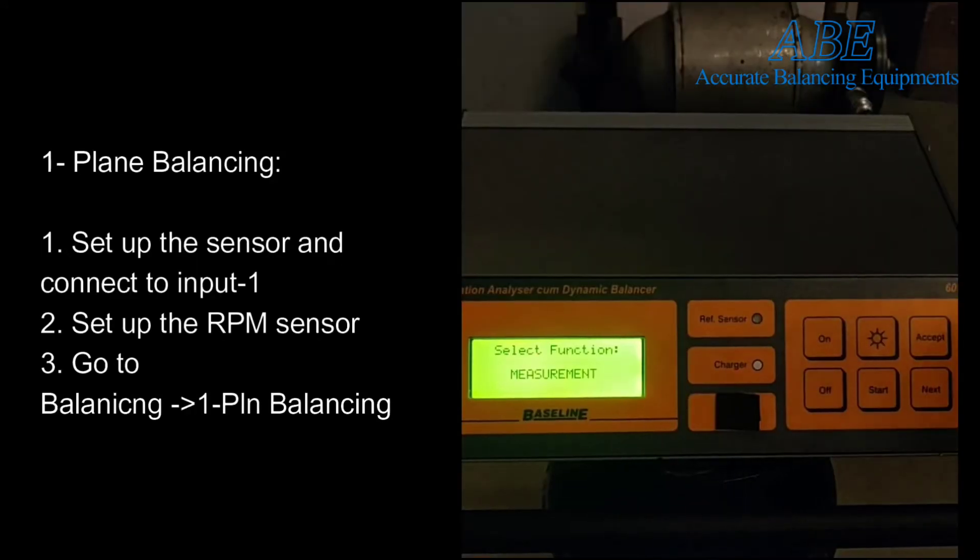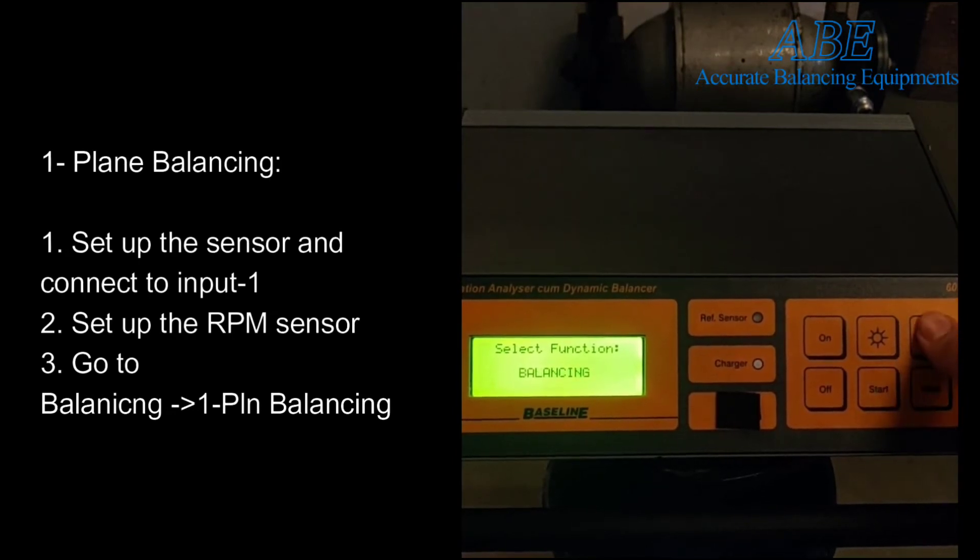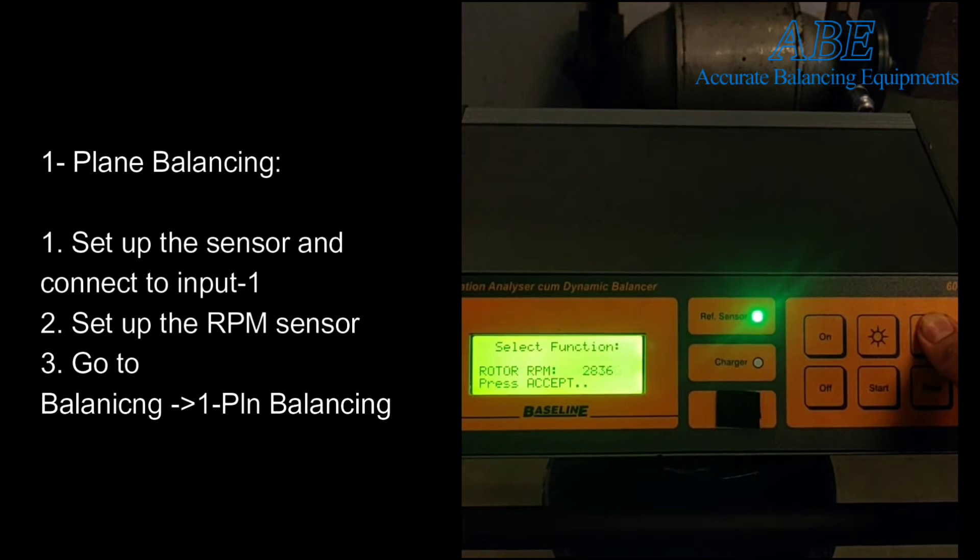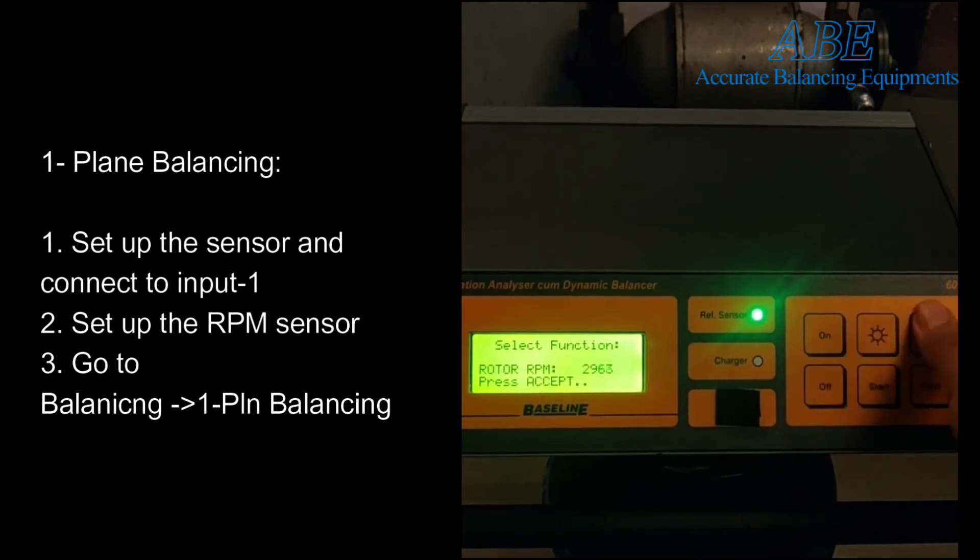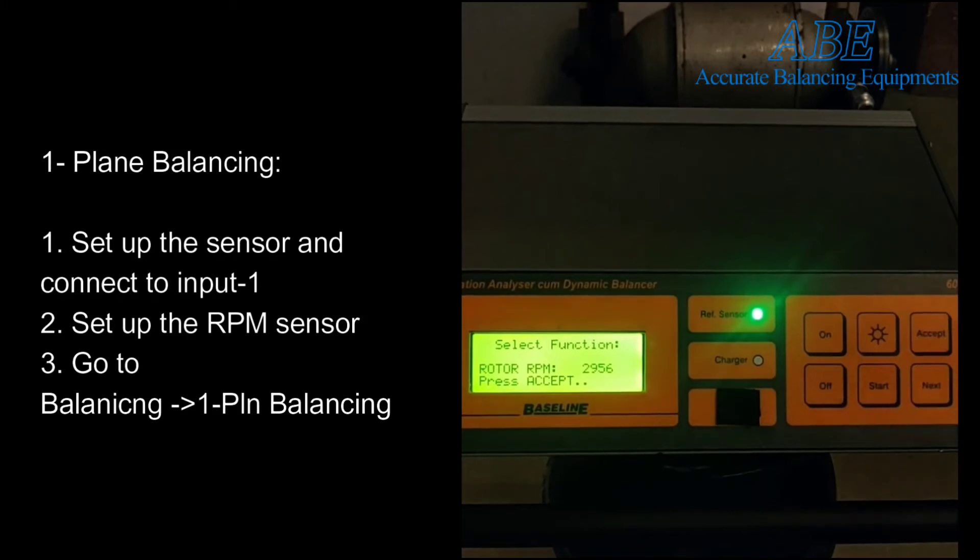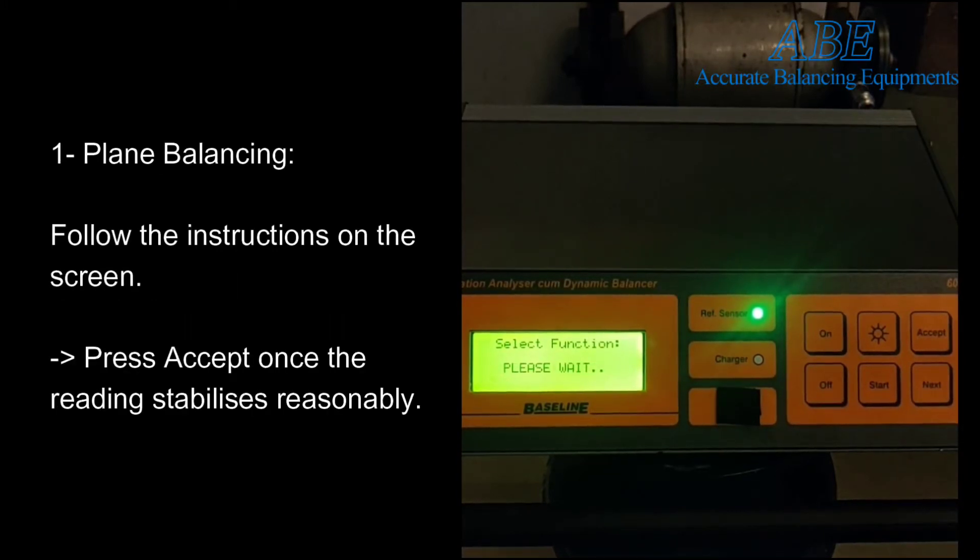Here is a demo of single-plane balancing using the 6050. Set up the unit for balancing as per requirement from the balancing setup. Set up the sensor and connect to channel one and suitably mount it on the rotor. Connect the RPM sensor for phase reference. Go to balancing, then one-plane balancing, then follow the instructions on the screen.